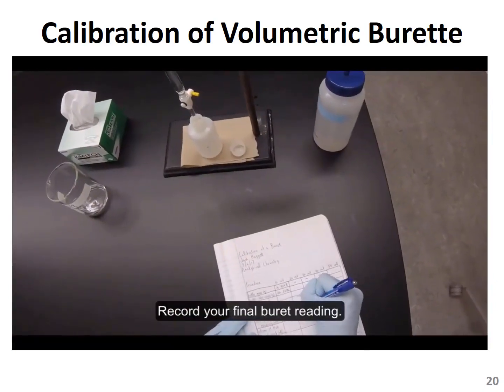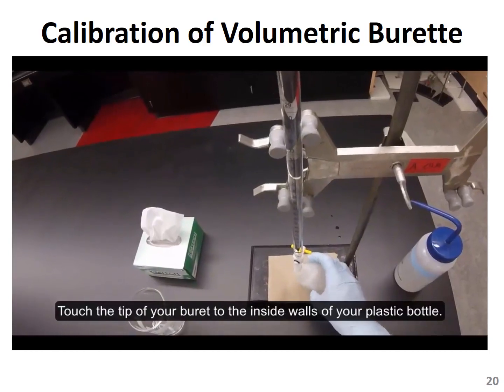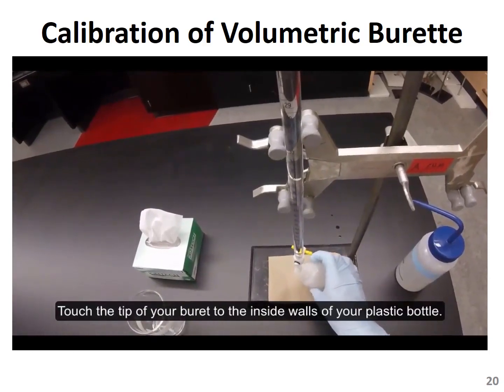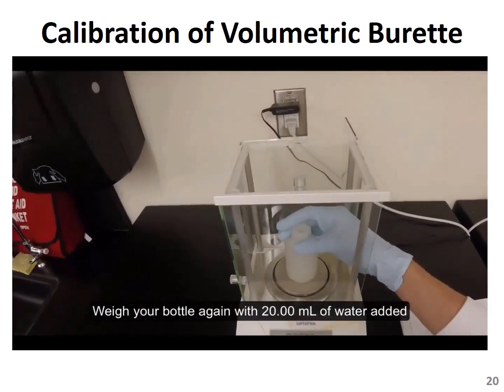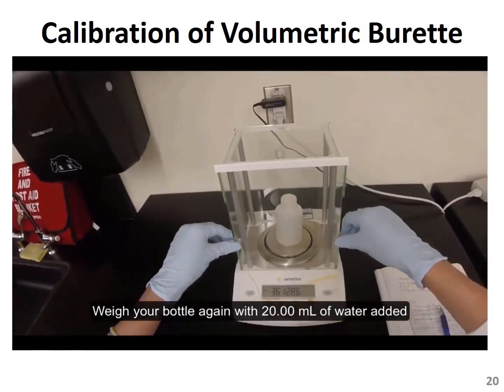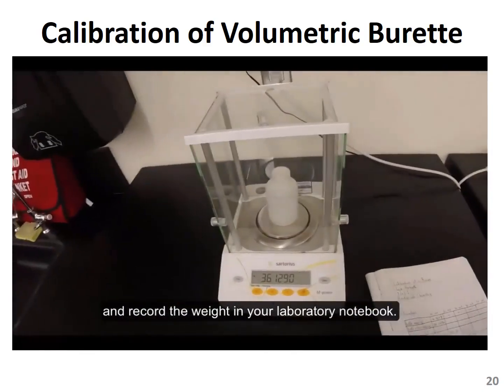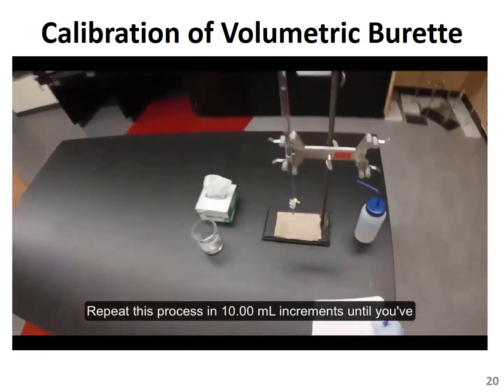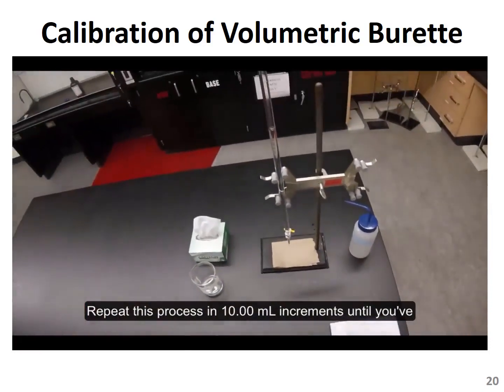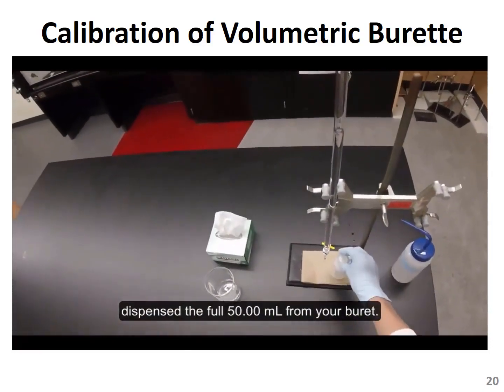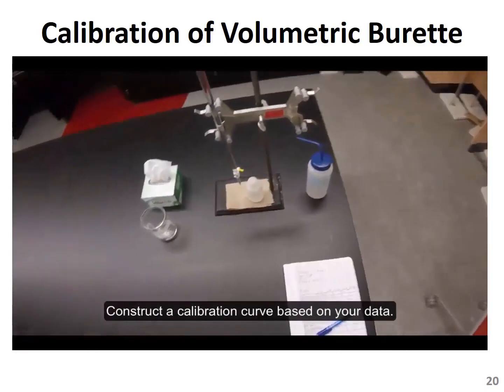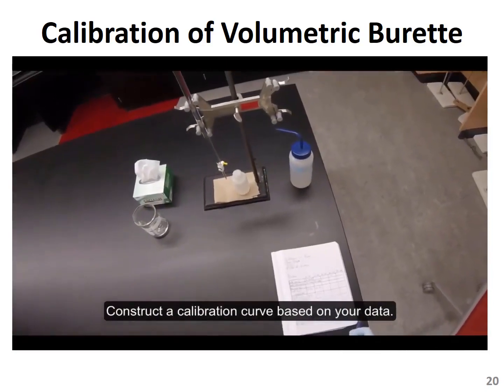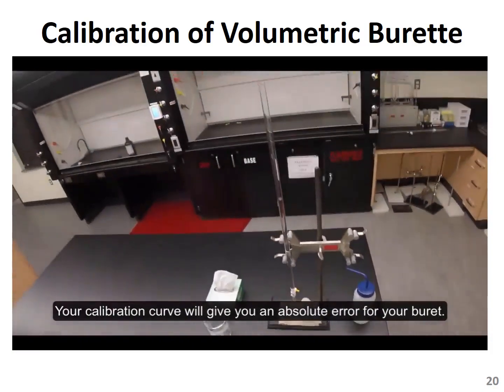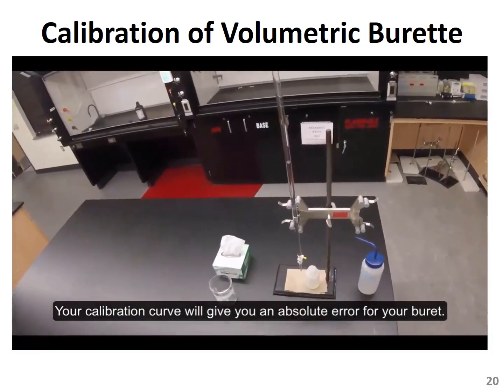Record your final burette reading. Touch the tip of your burette to the inside walls of your plastic bottle. Weigh your bottle again with 20 milliliters of water added, and record the weight in your laboratory notebook. Repeat this process in 10 milliliter increments until you've dispensed the full 50 milliliters from your burette. Construct a calibration curve based on your data. Your calibration curve will give you an absolute error for your burette.